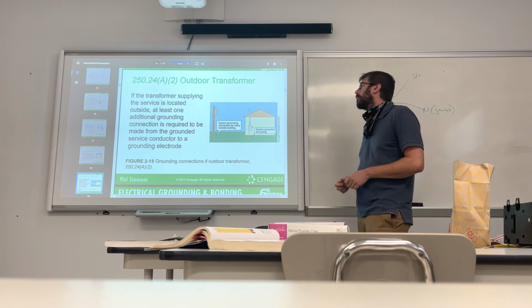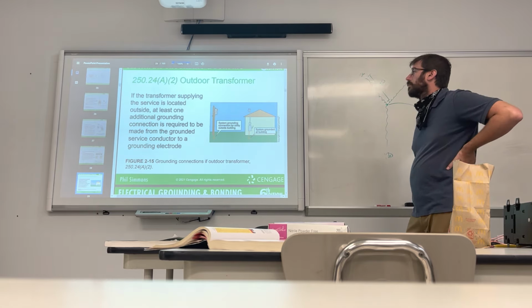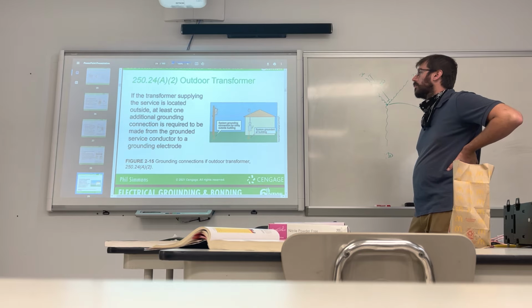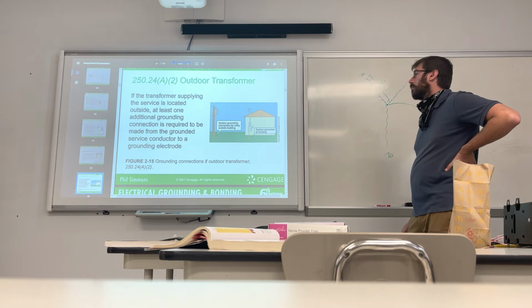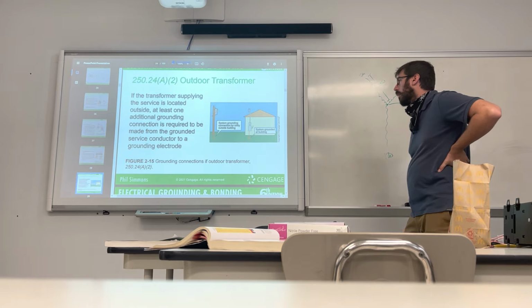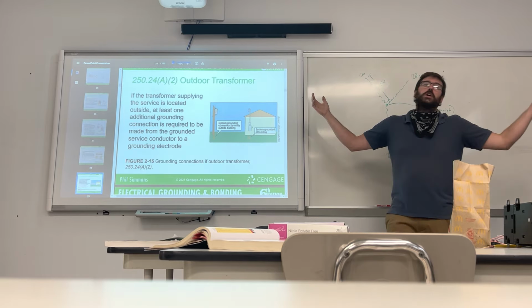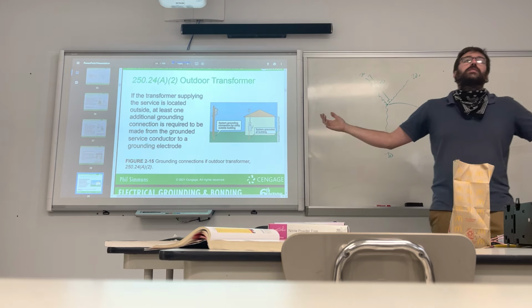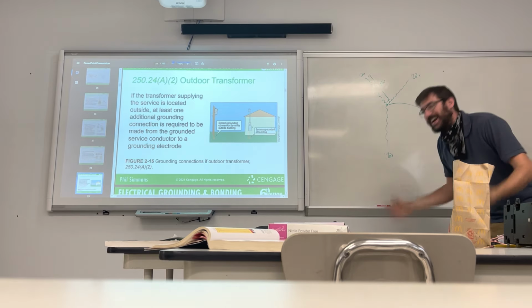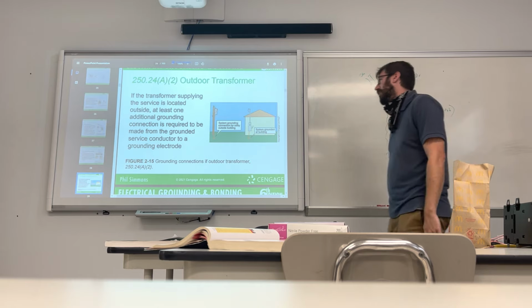Outdoor transformer: if the transformer supplying the service is located outside, at least one additional grounding connection is required to be made from the grounded service conductor to the grounding electrode. Is that shocking information to anybody? Have we said that 10 times already? Well, there's another slide telling you.